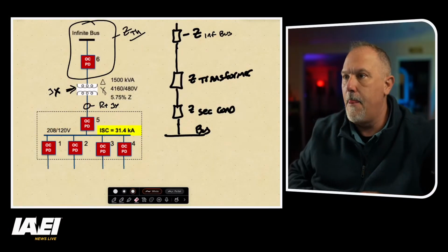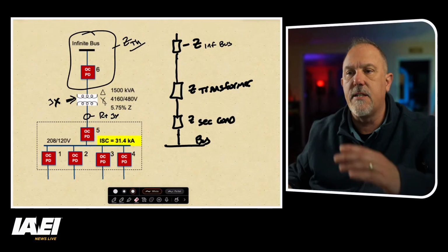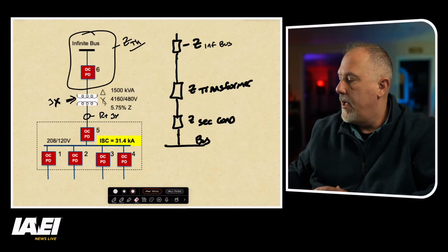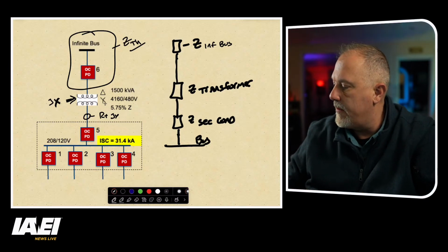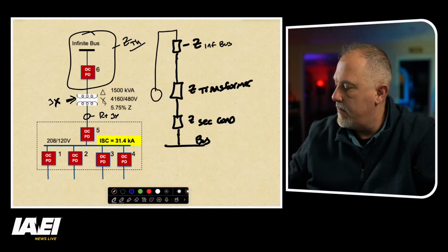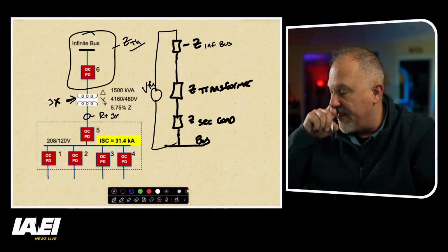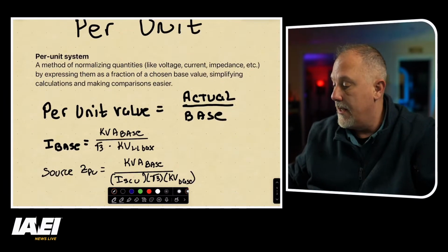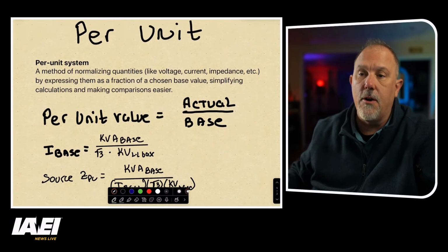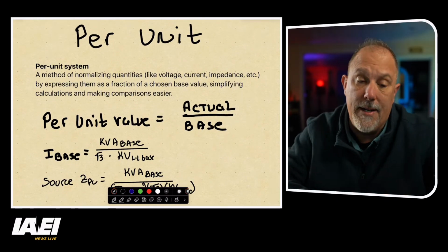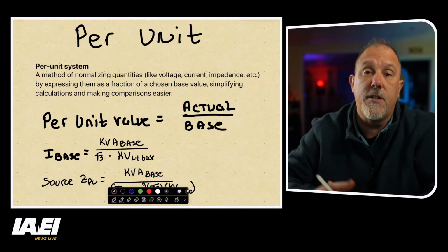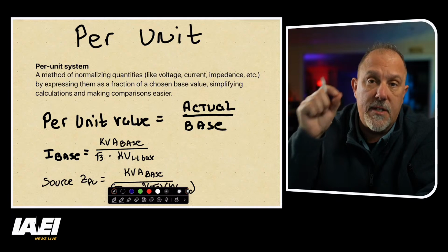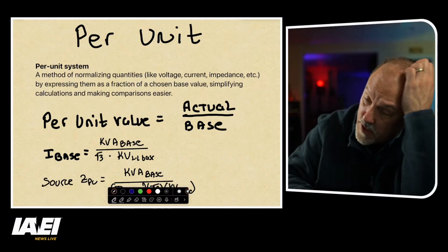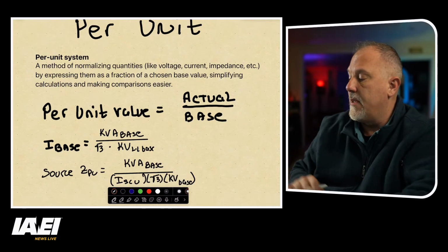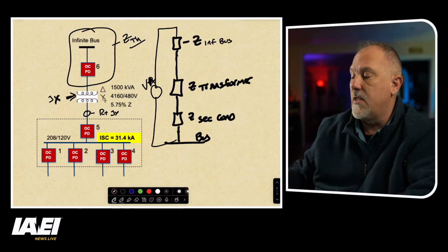So what we would do is basically represent this whole system in a one-line diagram and do a network impedance, where I have a Thevenin voltage and a voltage per unit, which is another term. Per unit values are actual over base. If you say, well, I never get into per unit, you do use per unit, because the percent impedance of a transformer is a per unit value. So you still use it, you just don't realize it. A per unit is an actual over a base.